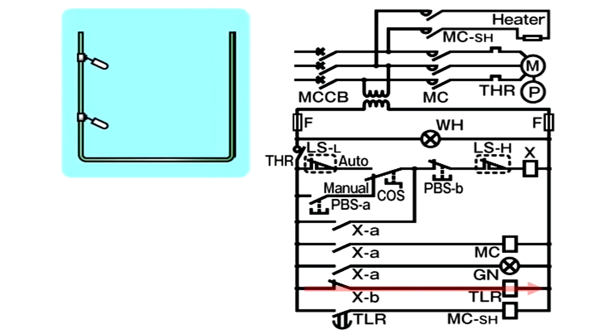Here the pump is operated immediately. As the push-button switch P-B-S-A is pressed, a current is passed from P-B-S-A to changeover switch C-O-S, to push-button switch P-B-S-B, to high-level float switch L-S-H, and to the coil of control relay X. Thus, the coil of X is excited.